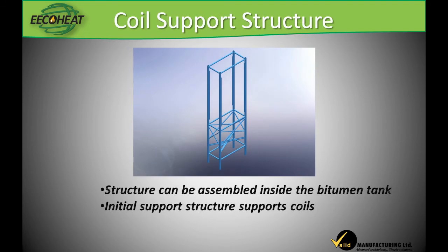Once the heat has been transferred into the thermal transfer fluid circuit, we need to transfer it again, this time into the bitumen tank. This is done by passing the heated fluid through a series of coils placed inside the storage tank. To support the heat coils, a fabricated steel structure is placed inside the tank. This structure, along with the heating coils, can be provided as a complete assembly or in kit form designed for retrofit installation.